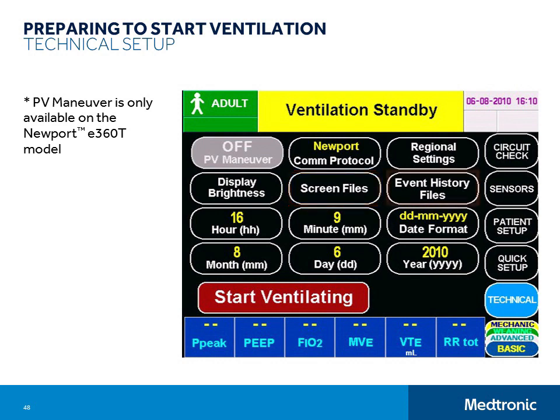After your first setup, you will only visit this screen to adjust screen brightness, download image or event history files to a flash drive, and if you are using the T model, to turn on the PV maneuver function. You can adjust technical settings and download files at any time during standby or while ventilating, but you must be ventilating in order to turn on the PV maneuver.